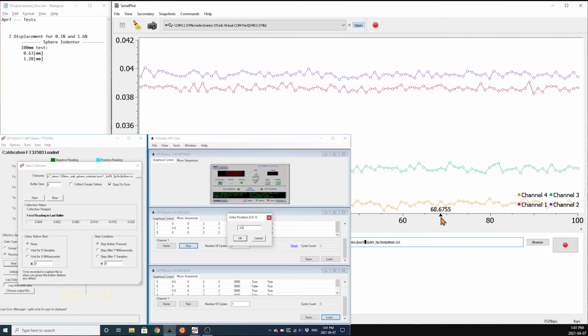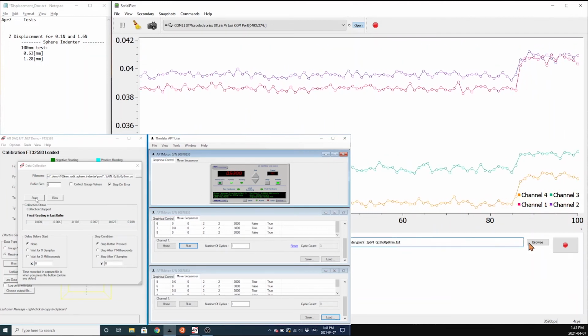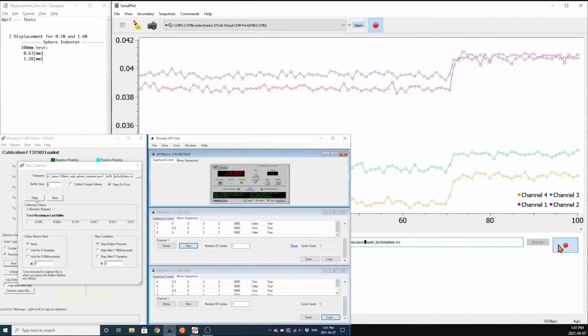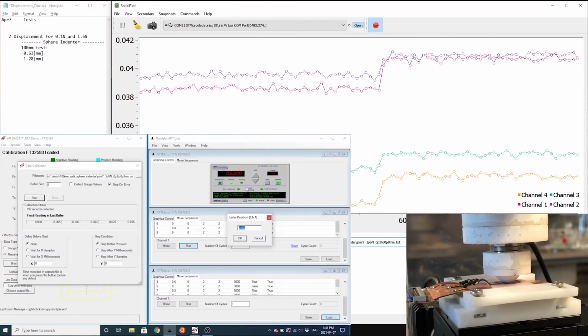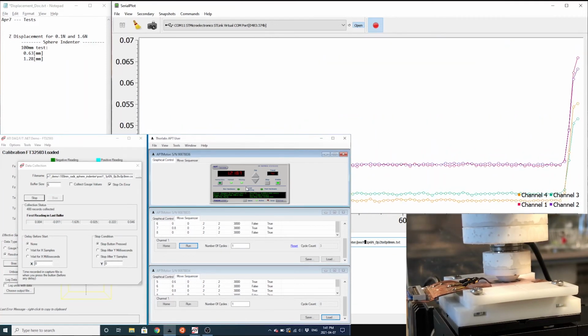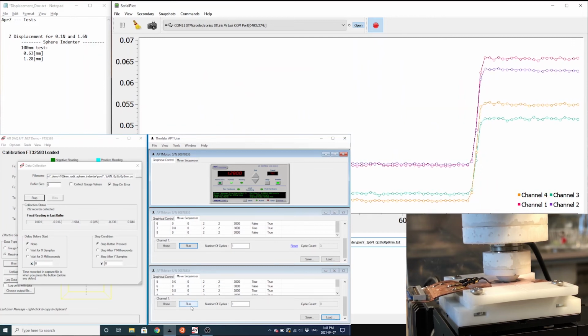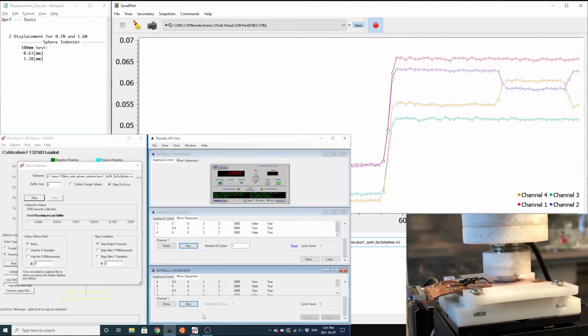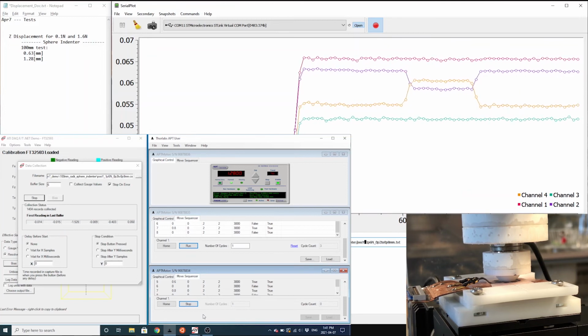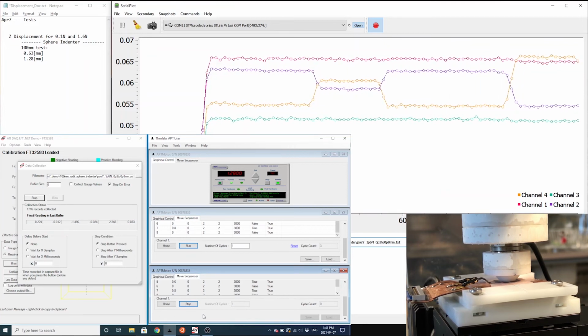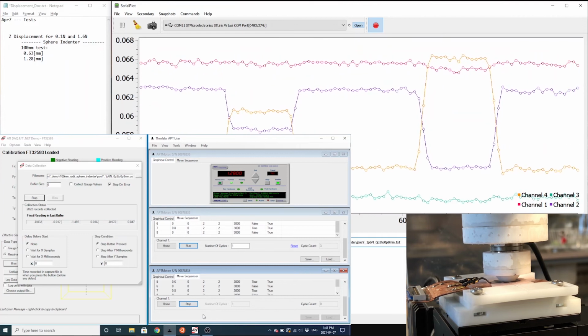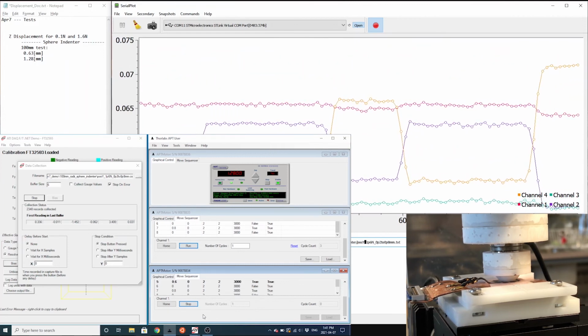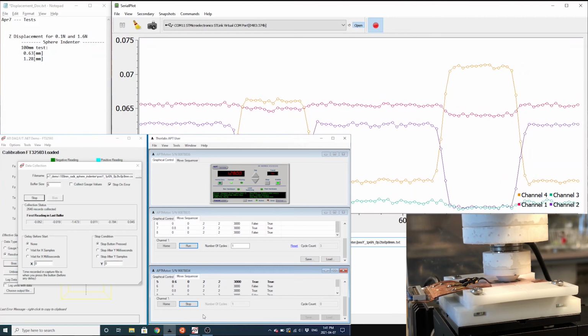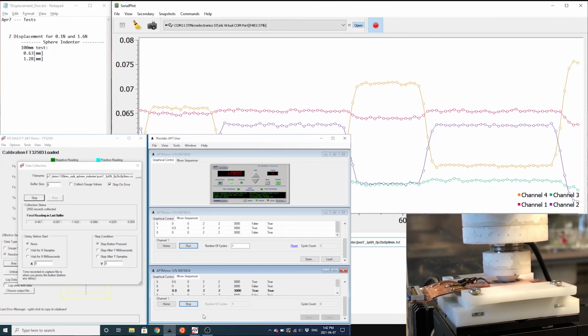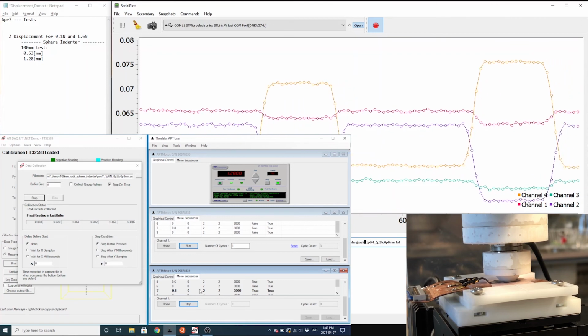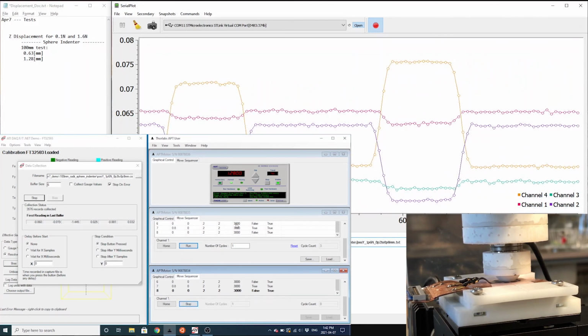Bring the sensor back up to 0.1 newtons. Repeat the same test, but now in the Y direction. These tests can be done with different normal forces, rather than just 1.6 newtons. After this test is complete, we can do the same tests, but now in the negative direction. This ensures all 4 directions of the sensor have been tested.